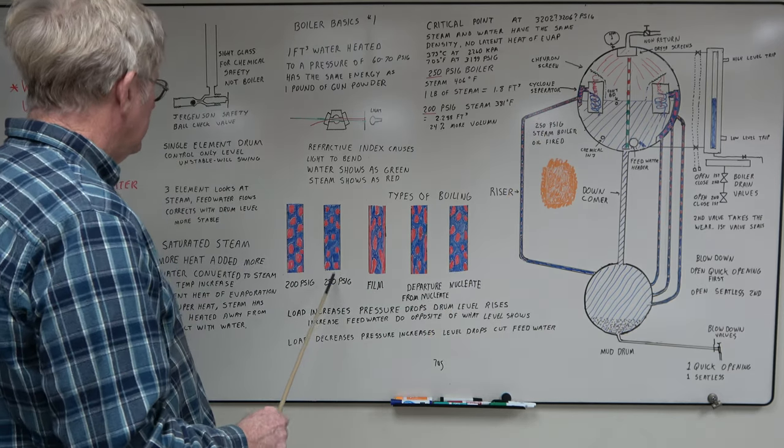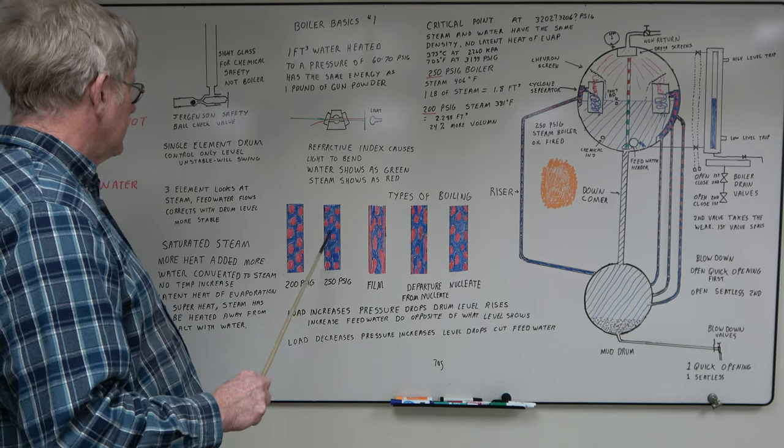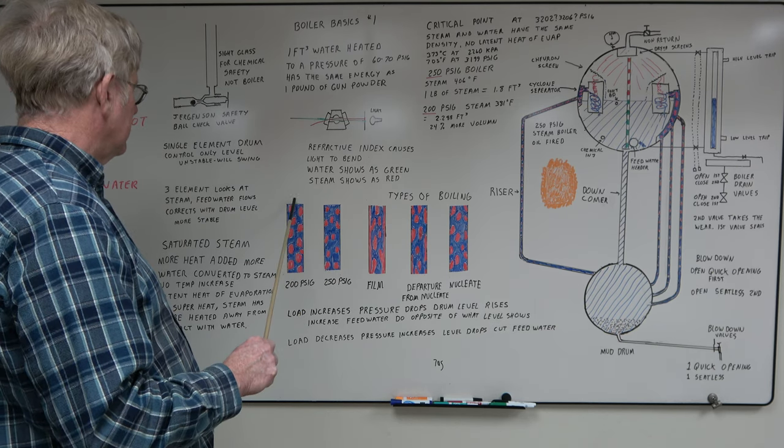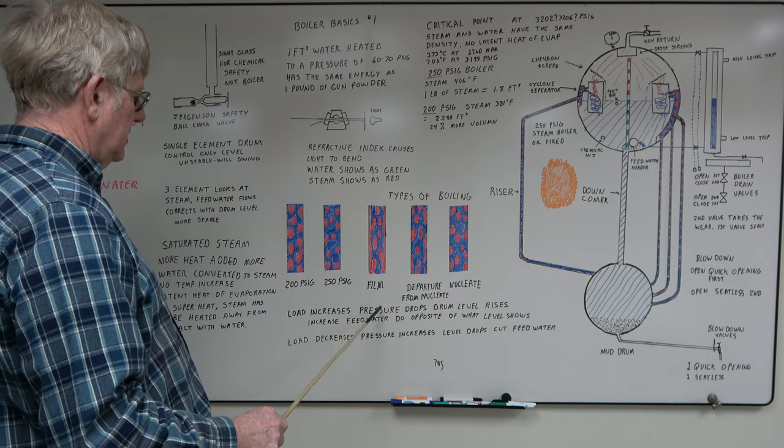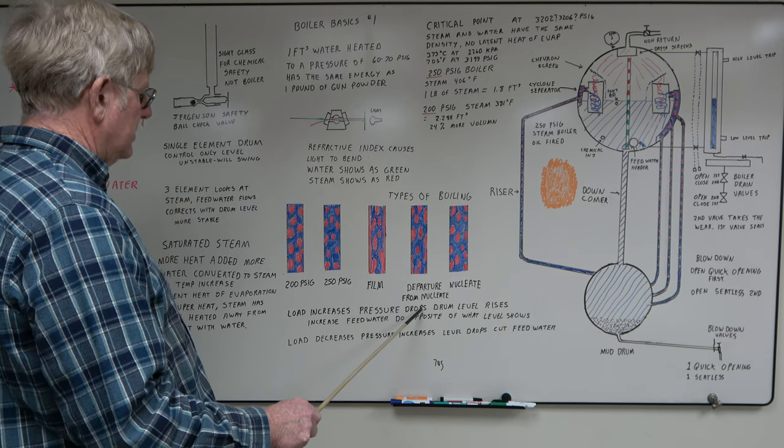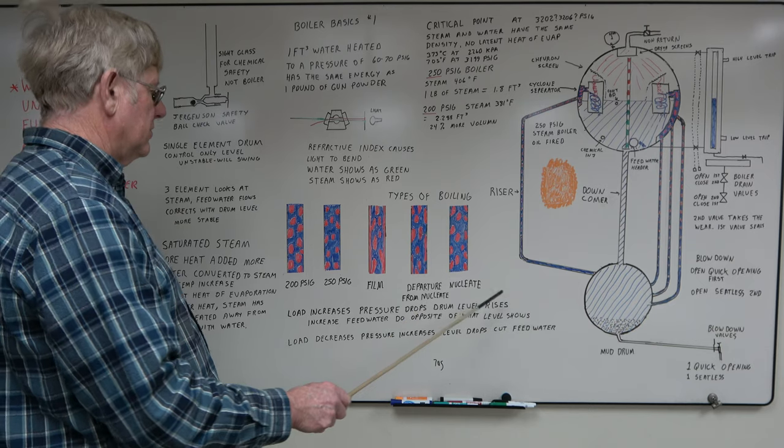It shows the 250 PSI smaller steam bubbles. If you drop this to 200, steam bubbles become a lot larger. You have a lot more volume. So as your load increases, the pressure drops, the drum level will rise.